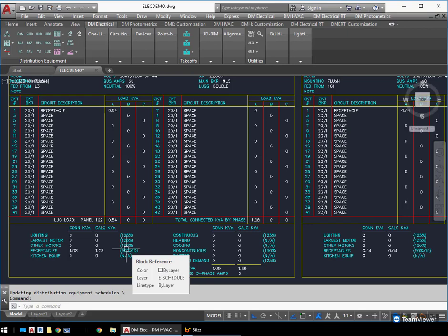And this means then, if you're using some of the multifamily dwelling calculations, the instance at the end of the run is going to be a single dwelling unit and is going to have one calculation that you can use. But if you're using the multifamily, if you have, say, 3 or 4 connected together, you can actually use the optional multifamily dwelling calculation and have a different footer for it.